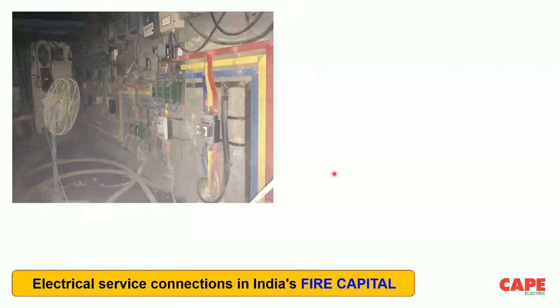In this particular picture, what you are seeing is a meter board, the electrical room, which belongs to the energy supply company in Bombay. You can see the wetness inside the room. The security fellow told us he was keeping the diesel of the generator inside this room. So what do you need more than this in case of an accident? Of course, you see a lot of fans. That means all the bus bars are hot and they have kept fans to cool them down. Such a situation shall not be allowed.